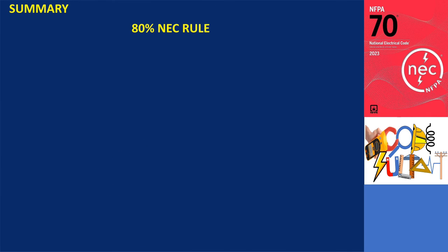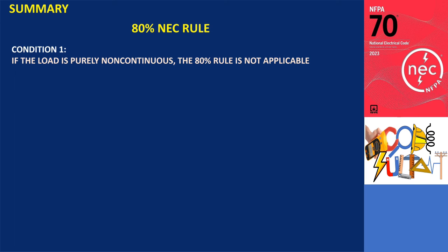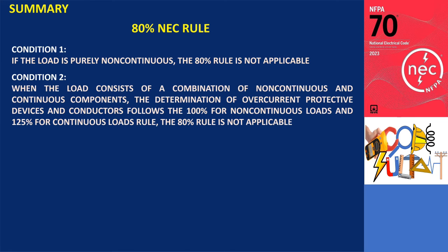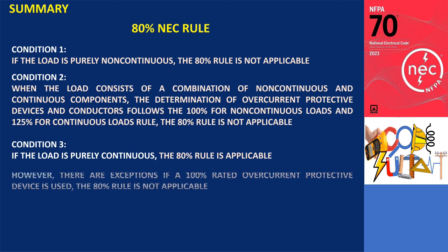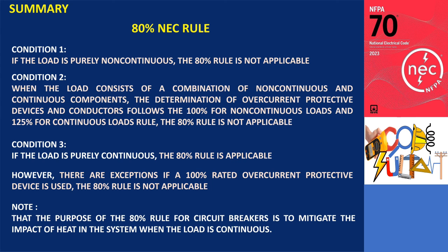In summary, the 80% rule specified in the NEC applies only in specific scenarios. If the load is purely non-continuous, the 80% rule does not apply. When the load is a combination of non-continuous and continuous components, overcurrent protective devices and conductors follow the 100% for non-continuous and 125% for continuous loads rule, excluding the 80% rule. The 80% rule is only applicable when the load is entirely continuous. However, if a 100% rated overcurrent protective device is used, the 80% rule does not apply. The purpose of the 80% rule for circuit breakers is to mitigate the impact of heat in the system when the load is continuous. Thank you all for watching.